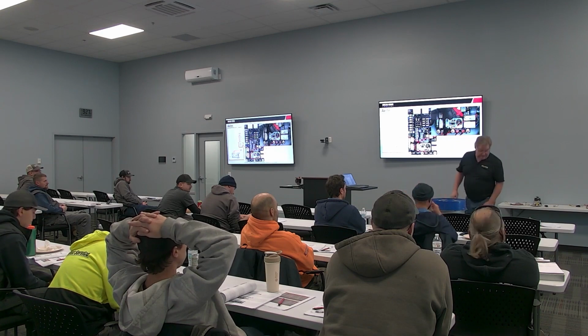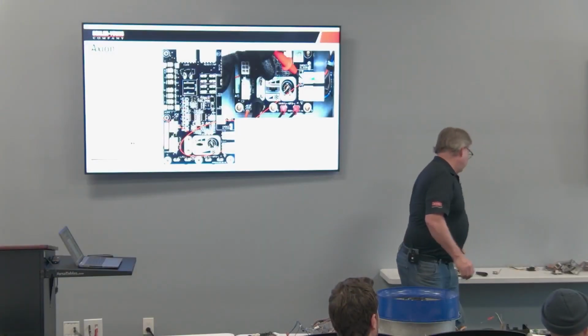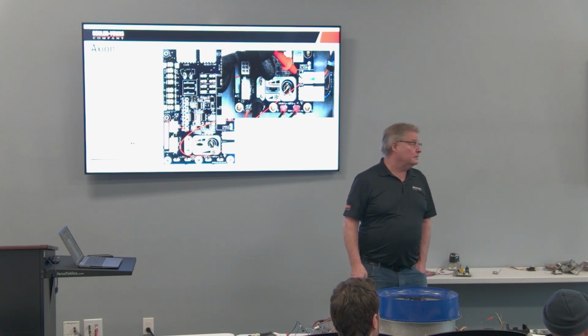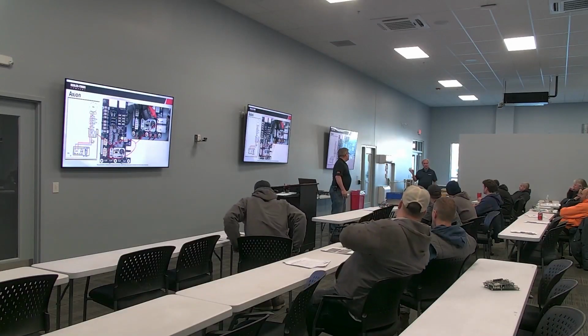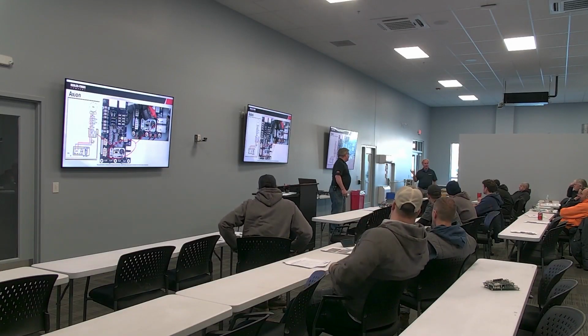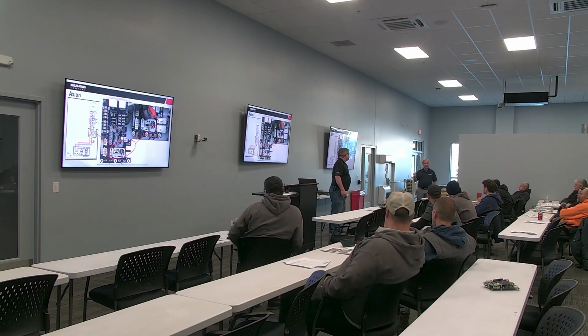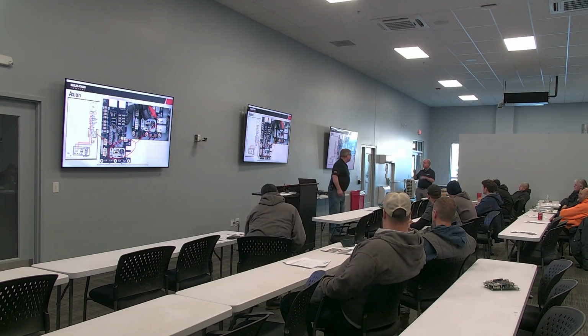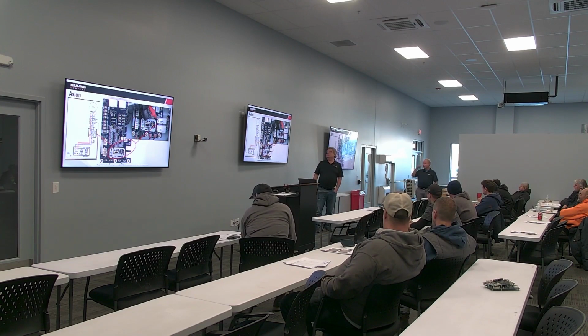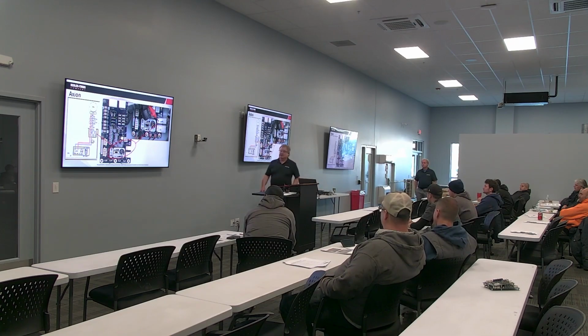Just a handy little tip: a lot of the contacts on the newer boards, especially if you're doing mini splits, are a lot smaller. So if you don't already have needle probes, make needle probes for all of your meters. Get a set of those, because it's a lot easier to get in there and actually make contact than trying to cram your big lead into the back of one of those. Good point.